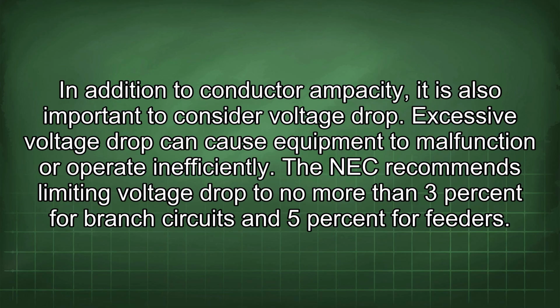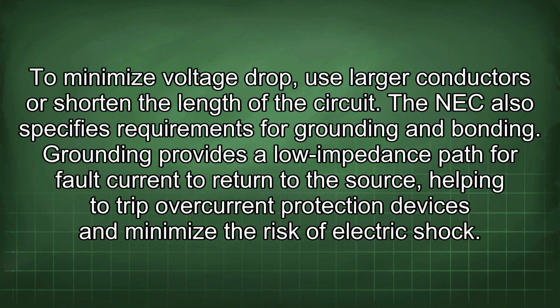In addition to conductor ampacity, it is also important to consider voltage drop. Excessive voltage drop can cause equipment to malfunction or operate inefficiently. The NEC recommends limiting voltage drop to no more than 3% for branch circuits and 5% for feeders. To minimize voltage drop, use larger conductors or shorten the length of the circuit.